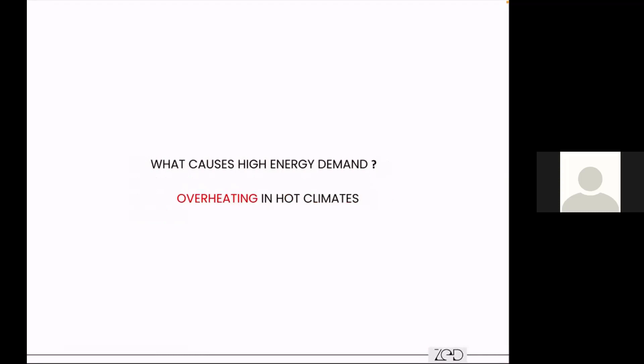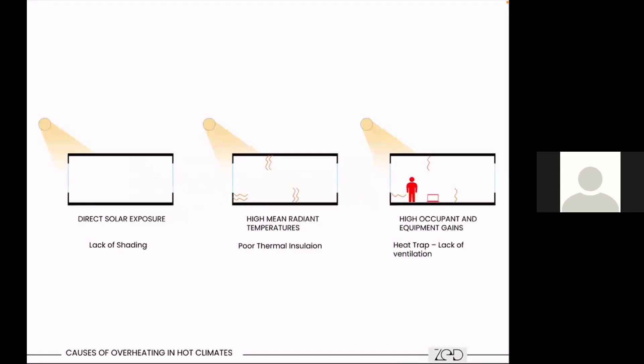What causes high energy demand and overheating in hot climates? The basic question is: do buildings actually need air conditioning during summers or heating during winter? In residential or any buildings where internal heat gains are not high, it is direct solar exposure and lack of shading, along with poor thermal insulation, which radiates a lot of heat through convective and conductive gain from outside into the building. Additionally, internal gains from high occupancy levels and equipment become a heat trap because of no ventilation and non-openable windows.